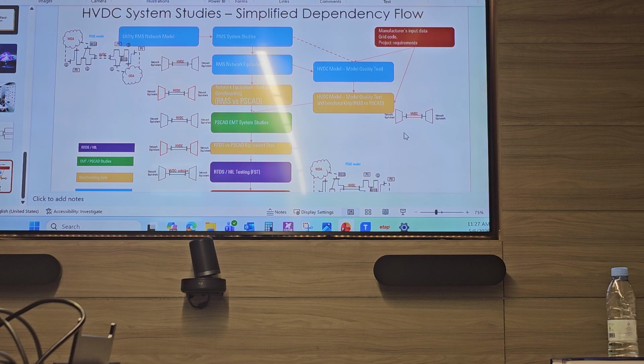When I simulate a short circuit and keep it for 300 milliseconds, and then it's cleared, the voltages and the system should remain stable. So it will go down, then something like this. And these curves I may even dig out from some studies. They put them in the same diagram in different colors, where they say this is PSS/E, this is PSCAD, and you can compare.